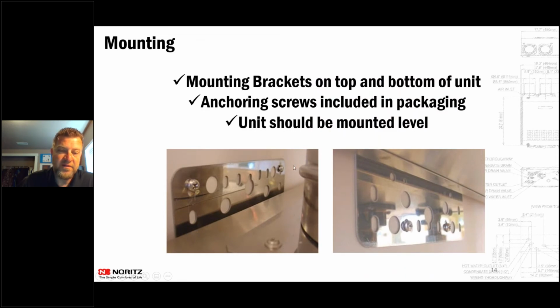So the top bracket is up here and the bottom bracket down here. Within the code, like with the tank water heater, you have the top third and bottom third for seismic. For these units, these brackets are your top third and bottom third. So when you are installing tankless water heaters, make sure you're affixing the top bracket and the bottom bracket. Don't just do the top bracket. I've seen a ton of those out in the field where people just mounted the top bracket and didn't do the bottom bracket.